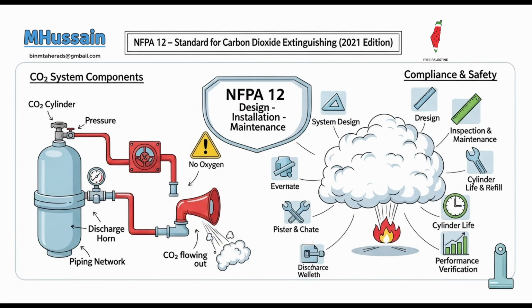What considerations are there for that venting aspect? That's a critical element that designers must consider. When CO2 rapidly expands from a liquid to a gas, it creates significant pressure buildup. Without adequate venting, this pressure could compromise the structural integrity of the enclosure itself. Furthermore, the rapid influx of CO2 displaces not just oxygen, but also any flammable vapors, and these need a safe way to escape. Gotta let the pressure and bad fumes out.